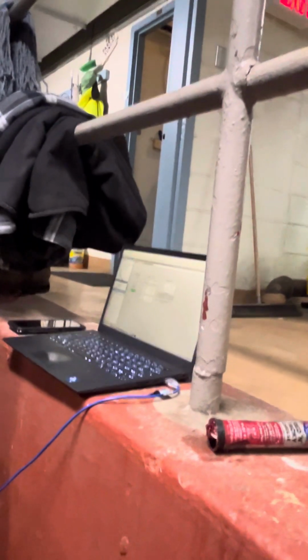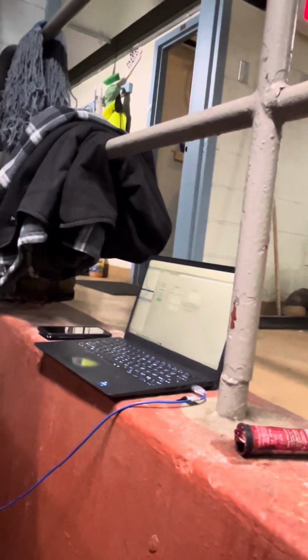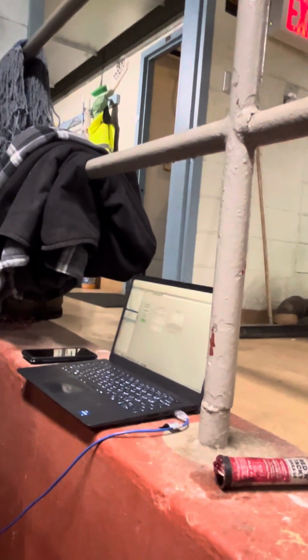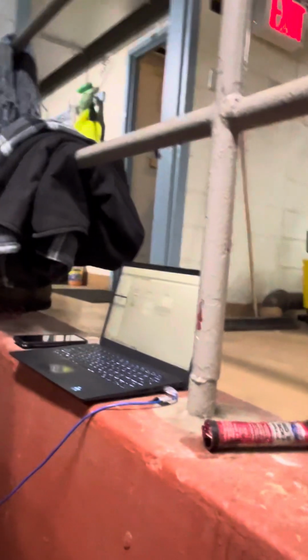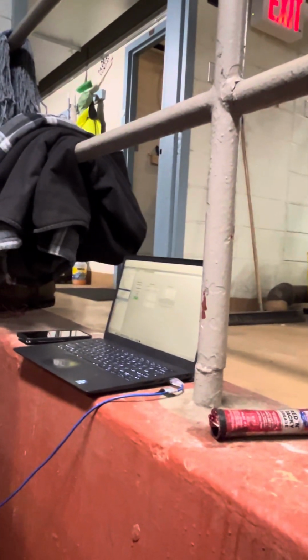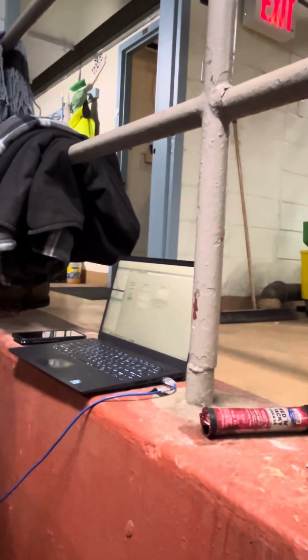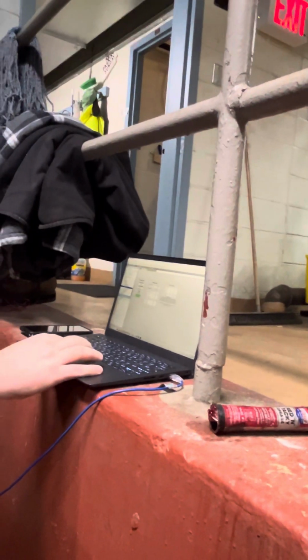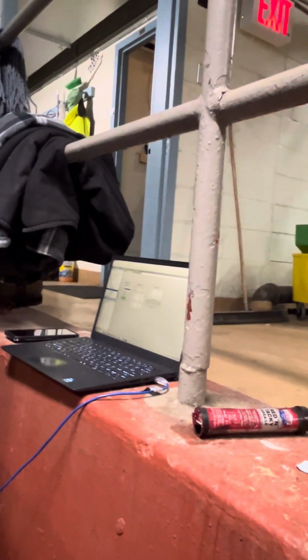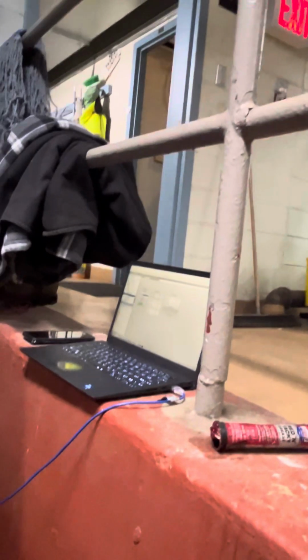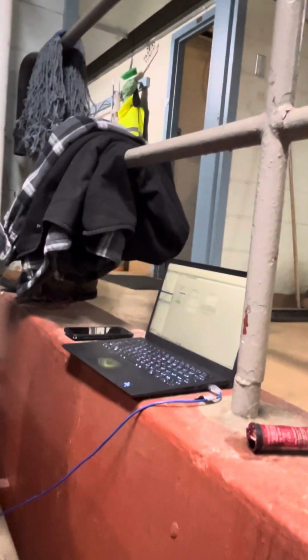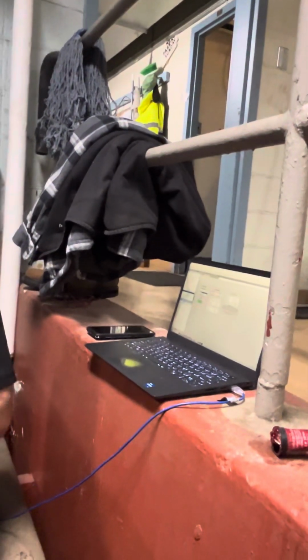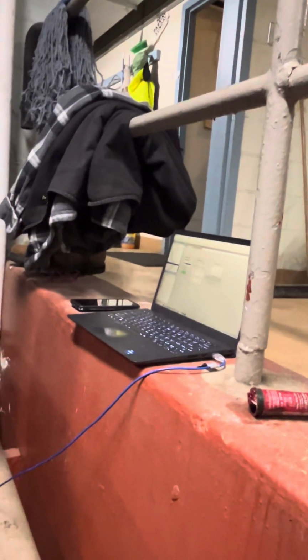If you're bound by something with the state, or whatever, due to funding, and you can't go with that, I'd say lower that all the way down, or you should be able to hit this system enable point and override it to disable, to keep the system locked out if you can't start your boilers before a certain date, or need to shut them down by a certain date. You can just hit that master system enable, override it, and then you don't have to worry about the outside air — it will shut these boilers down altogether.